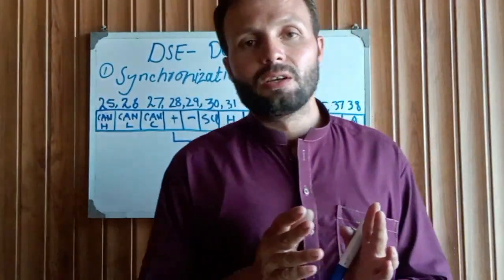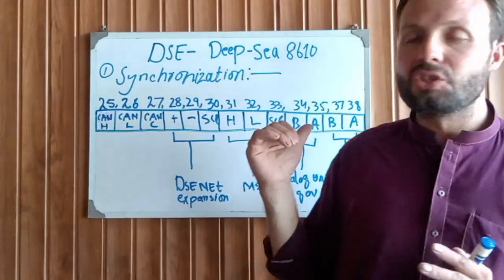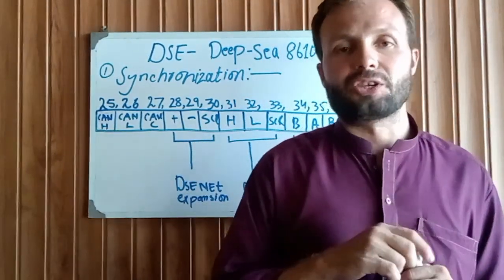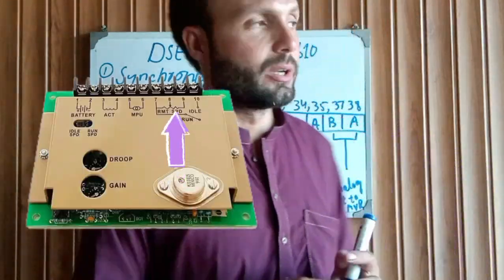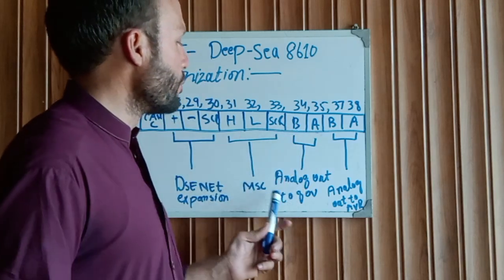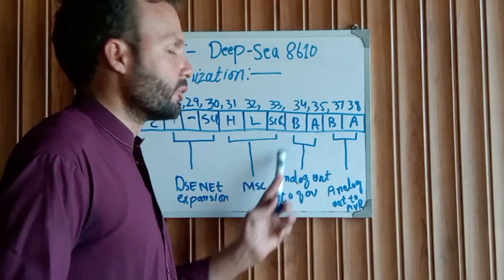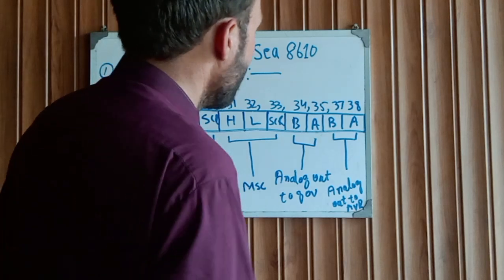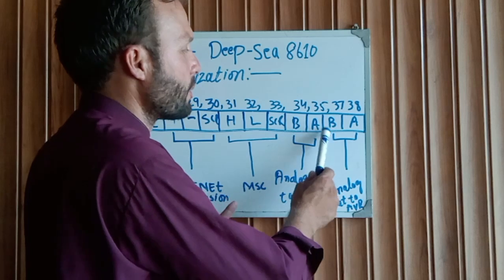This DC supply is going to our governor potentiometer place, which we control remotely. Put these two wires on your governor potentiometer terminal connection, which is sometimes used for remote control operation. Remove the remote control operation and connect these two output wires from the DSE 8610 to your governor potentiometer or governor control card potentiometer.